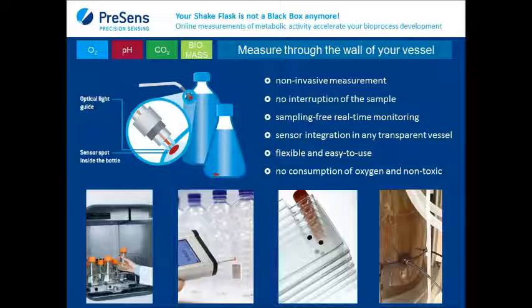The benefits of an optical measurement is that it is a non-invasive measurement. You don't have to interrupt your process to draw a sample from your flask or from your vessel. It's sampling free, and that means it gives you a real-time monitoring of the parameters. You can integrate the sensors in any vessel, so it's a very versatile technology. It's very flexible and easy to use. And if you're using it at very small volumes, it might be interesting to mention that oxygen is not consumed during the detection. And also, all the sensors that we manufacture are tested for leachables and extractables, so they are not toxic and they're FDA approved or USP Class 6 approved.